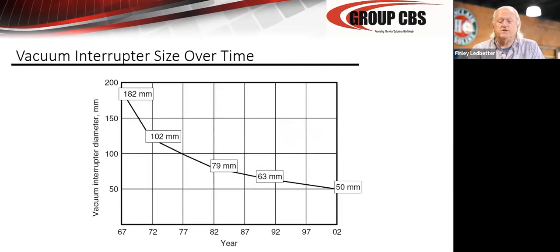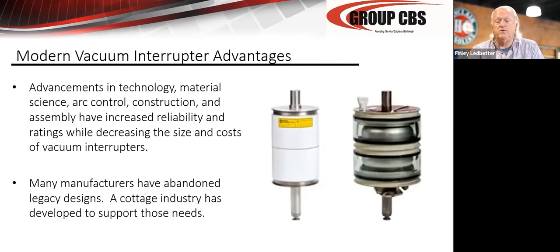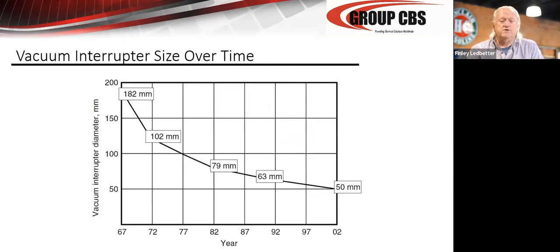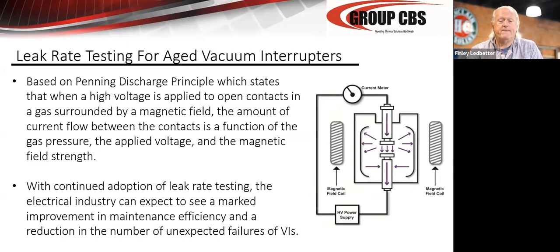Vacuum interrupters have gotten smaller over the years. If you look at this, the one on the right and the one on the left are the same rating. So don't be surprised when you see a replacement breaker, a vacuum interrupter, or a new breaker that has very small interrupters with a high interrupting rating. Because as you can see, over the years, the standard interrupter has shrunk, and they're going to continue to get smaller as everything does.